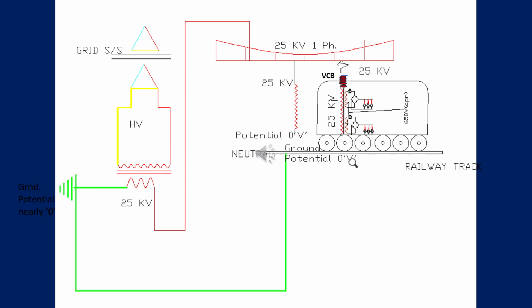Auxiliaries means this traction motor is taking tremendous current and it needs help. Not only the traction motor, the rectifier is also going to be heated. The transformer, the smoothing reactor, that means this inductive coil, all are getting heated. Then the transformer oil also needs cooling. So all these functions we are doing with these auxiliary motors. We are using blower motors, silicon rectifier blower motor. So many blower motors are there.